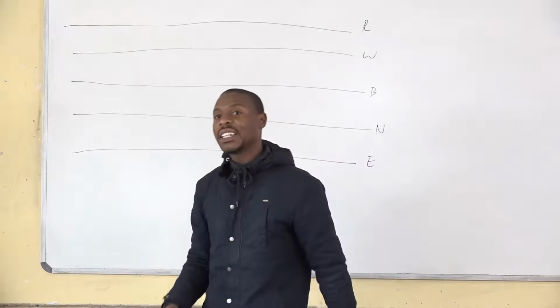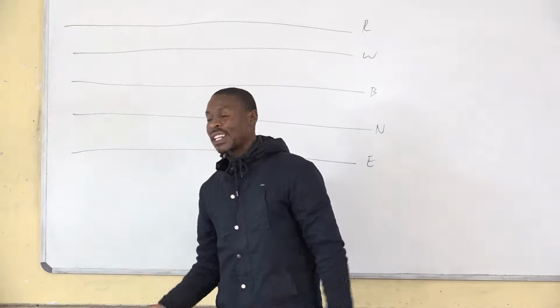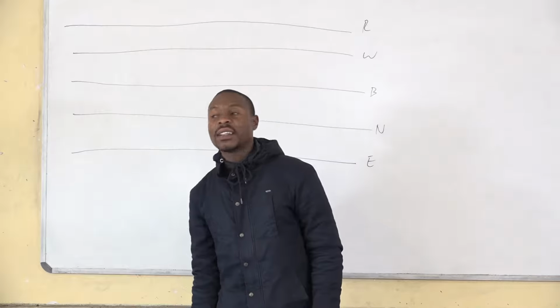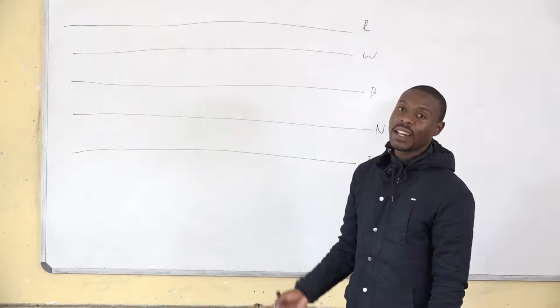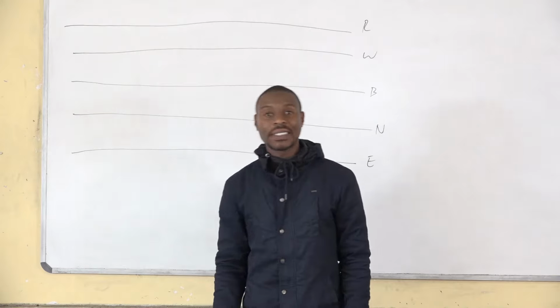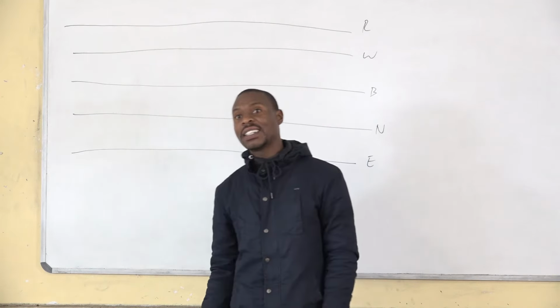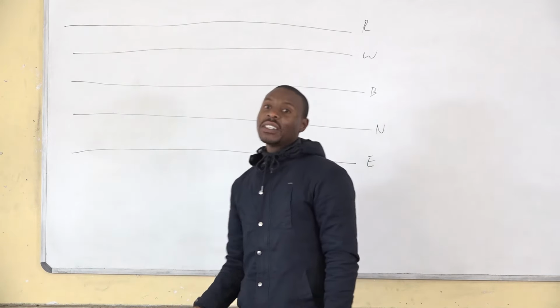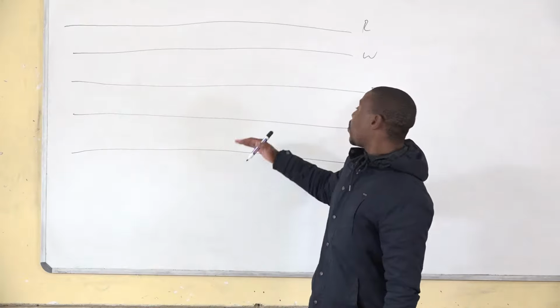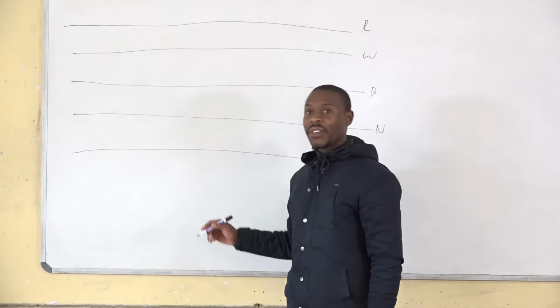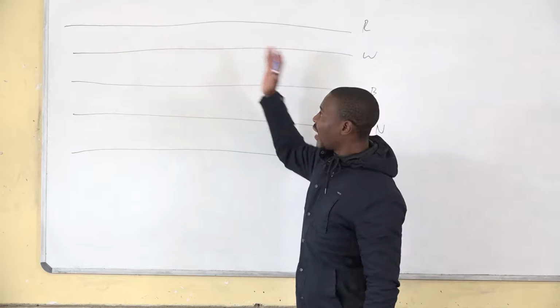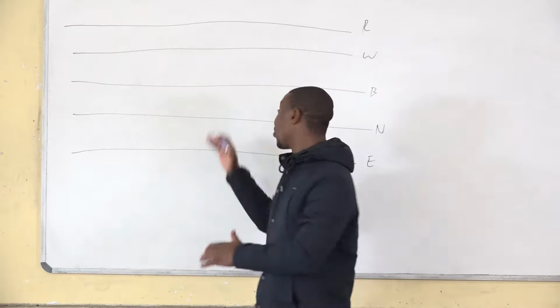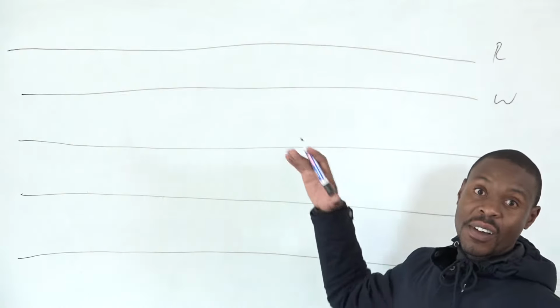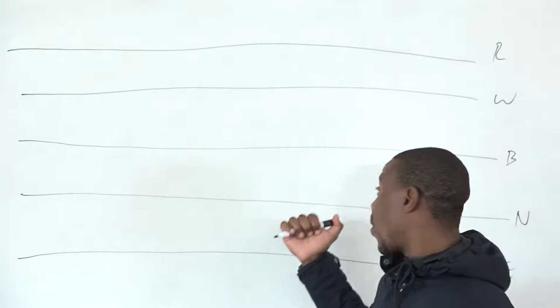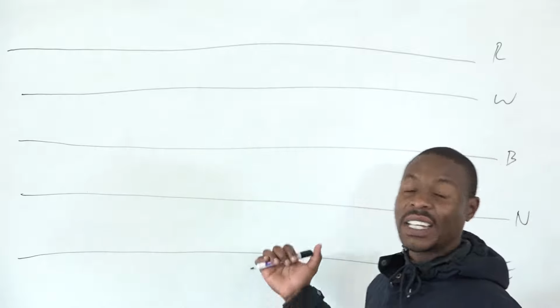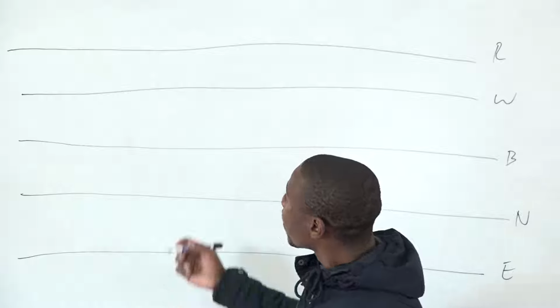The reason for balancing a load is this. Remember, our transformers are rated in kVA. So for instance, if we are given a 50 kVA transformer, we mustn't exceed that kVA, or else the transformer will explode. So we are balancing a load. By balancing a load, what do we mean? Each phase must carry the same load. No line must be pulling more voltage or wattage than the other one.